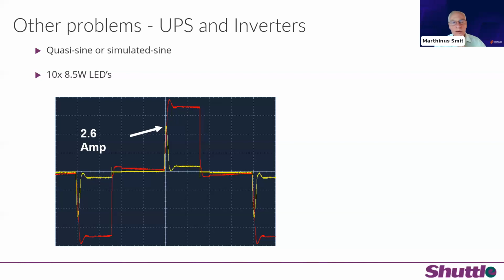Now, lastly, and this is also becoming very, very important, because of the load shedding in the country, many companies and many people are moving over to inverters and so on. And very often we find that the contractors or the installers do not pay any attention to the lighting requirement when they do the load calculations, because the logic is to say that if I have 10 8.5 watt LEDs, it's 85 watt. It's nothing compared to the geyser, which is 2.5 kilowatt and so on. But it may not be correct.